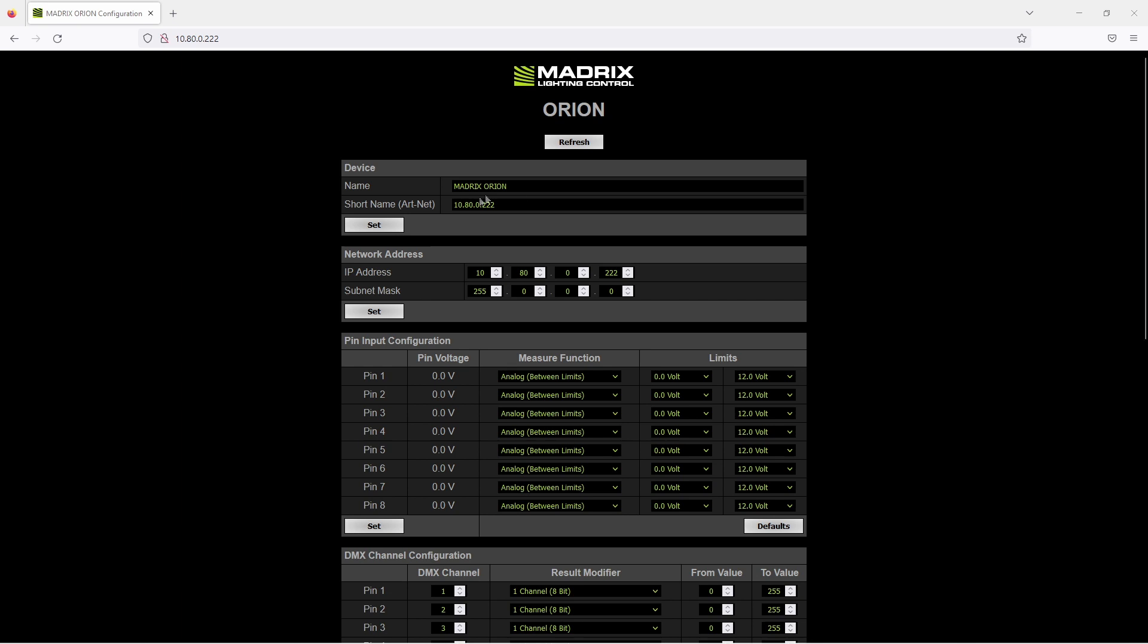In the next section, the network address, you can change the IP address to your desired IP address and of course also the subnet mask. But please pay attention: if you change the IP address of an Orion and you don't know where you have set the IP address, you won't get access to it because after setting the IP address it will be called with this IP address.